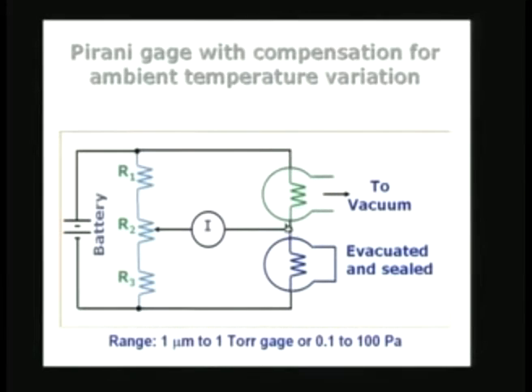As we discussed in thermometry, if you have a resistance element and pass a current through it, its temperature increases, and as the temperature increases, the resistance of the element also changes. So the change in resistance is what is measured — just as in thermometry — but here instead of relating the resistance change to temperature, we link it with the background pressure. This is essentially the RTD principle, and it is called the Pirani gauge. Here is the schematic of a Pirani gauge.